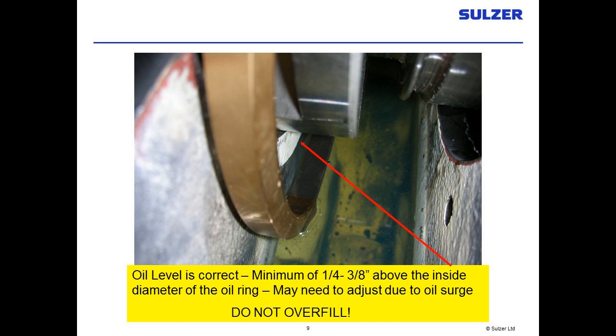Oil-lubricated bearings are a little different. We have to maintain a certain level of oil in the reservoirs — not too much, because we depend on a brass ring to revolve in and out of the oil and bring lubrication to the top of the shaft. Too much oil creates drag on this ring and slows lubrication. Look at your sight glass on the side of the motor — it's designed to be measured at standstill with the oil level at the midpoint. Don't overfill it; the oil level will look low when rotating, but filling it full will cause oil leaks on the outside of your motor.